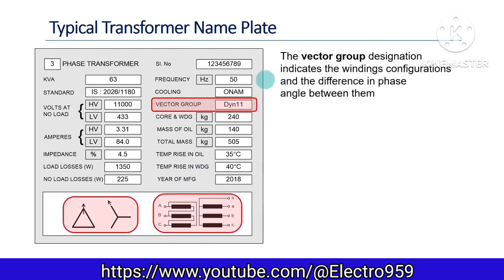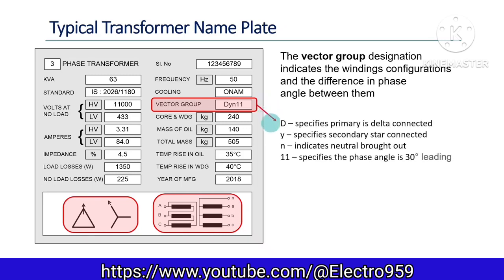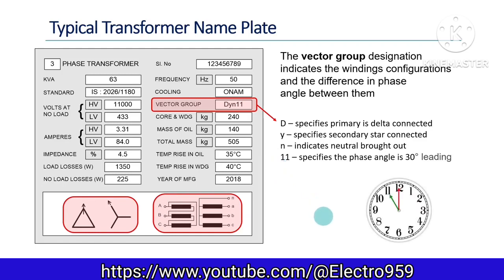The vector group designation indicates the winding configurations and the difference in phase angle between them. The uppercase letter D specifies the primary is delta connected. The lowercase letter Y specifies star connection in the secondary. N indicates that the neutral terminal is available, and the number 11 specifies that the phase difference is 30 degrees leading. The number 11 corresponds to the hand position of 11 o'clock on the clock dial, where the angle between the clock hands is 30 degrees.